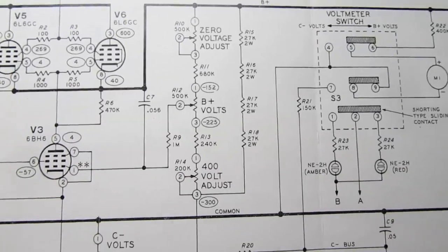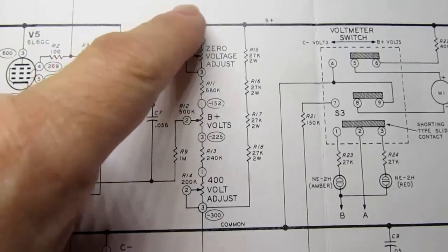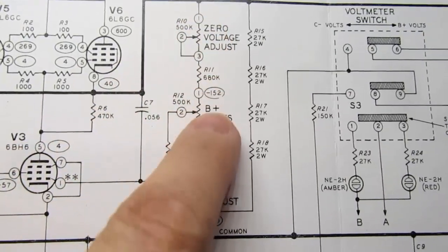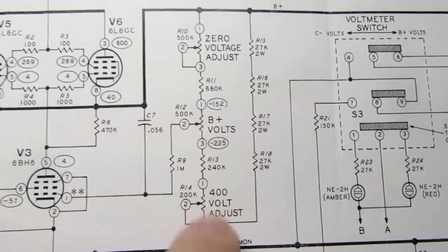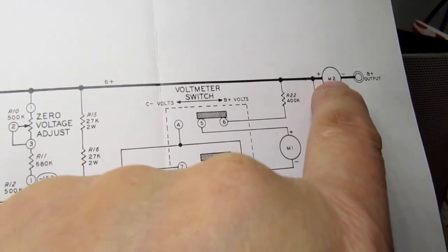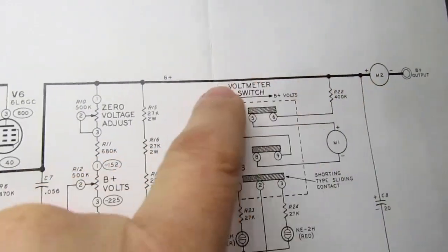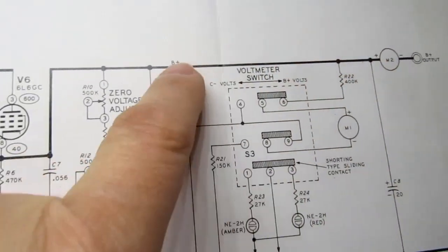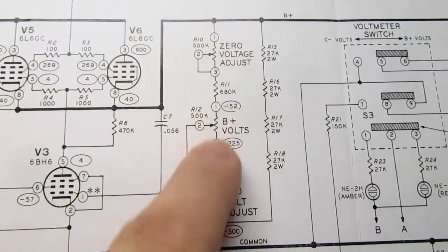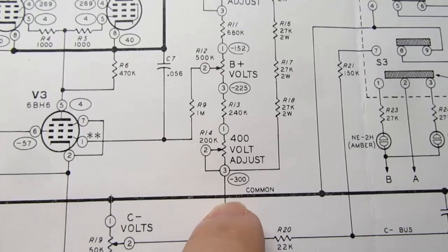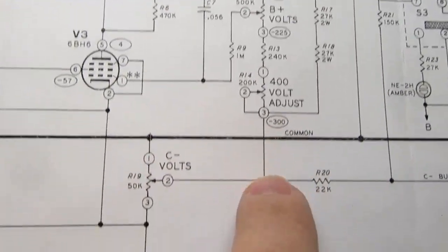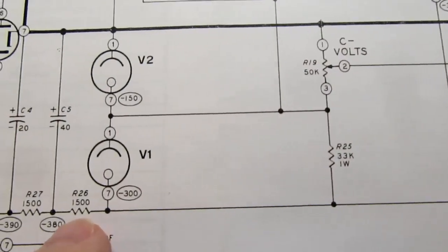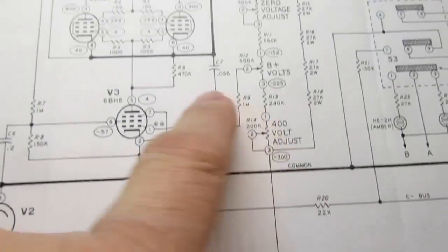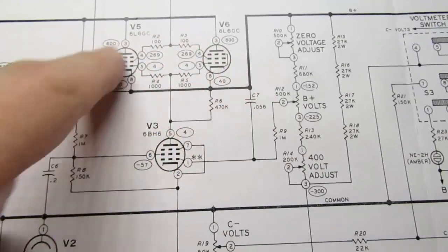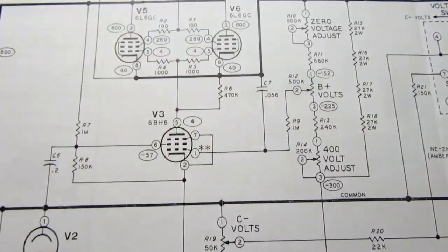So in order to have a regulated supply, you need to have some feedback. So that feedback is achieved here with this series of potentiometers and fixed resistors, and they come right from the output upstream of the milliamp meter, and that's going to have a really low resistance, so negligible. The other side, and these all form a big voltage divider, but notice that the bottom side of that does not go to the circuit common. Instead, it goes way down here to the minus 300 volt power supply. And that all has to do with the way these three tubes need to operate, in which voltage domain they're operated, even though the output will only be positive relative to circuit common.